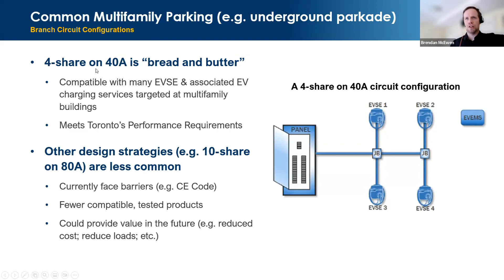There are certain strategies that probably aren't viable now under the electrical code, but there are active code change proposals at CSA Group to make them viable - allowing, say, 40 amp chargers on 80 amp circuits. Once that's enabled, there might be greater value in configurations with higher amperage branch circuits sharing across larger proportions of parking spaces. It's worth monitoring that space. It won't save huge amounts, but it's marginal and can also provide good quality of service for drivers. For the time being, 4-share on 40 amp is a pretty sensible configuration.